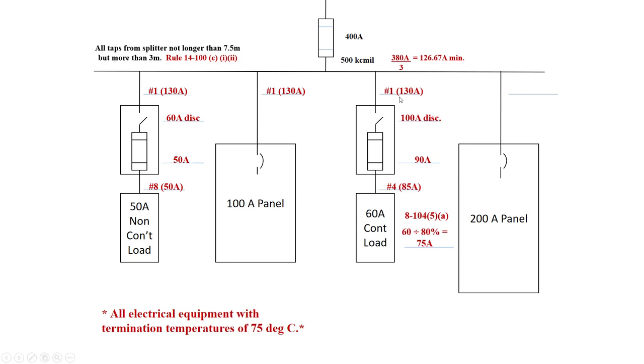The last one, the 200 amp panel - to safely carry this load, we would have to go to table 2 and look up under the 75 degree column 200 amps. We would have to pull three aughts out, rated at 200 amp. The 200 amp exceeds the one-third, so we're good to go. This one sized based off the load and it exceeds the one-third of our 500 KC mil. Hopefully that helps you out. We'll see you on the next video.